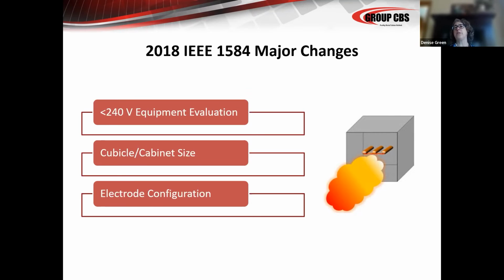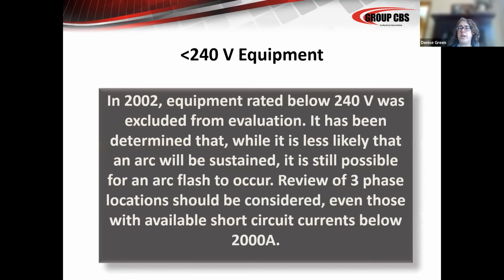Prior to 2018, there was no arc flash labeling requirement or calculations for equipment at that voltage class and below. Over 16 years, when working with the NFPA, they saw that arc flash incidents were happening, where people were getting injured on equipment 240 volts and below. So there was a determination that now that should be a piece of equipment that should be evaluated, and potential labels created for equipment 240 and below.